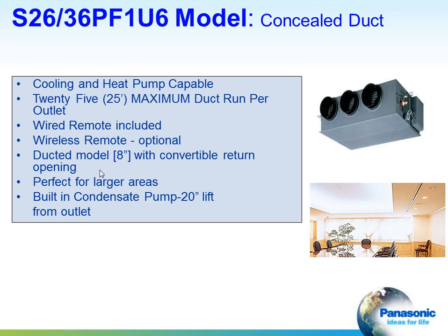There's a maximum duct run of just 25 feet. You can use flex duct, but of course local code usually requires a maximum of about 5 feet of flexible duct on these, depending on the jurisdiction that you're in. Wired remote is included, and there are also some options on the return openings. Good for larger areas where you might need to reach multiple rooms. You can do that with this single unit, and there's a built-in condensate pump in this as well.